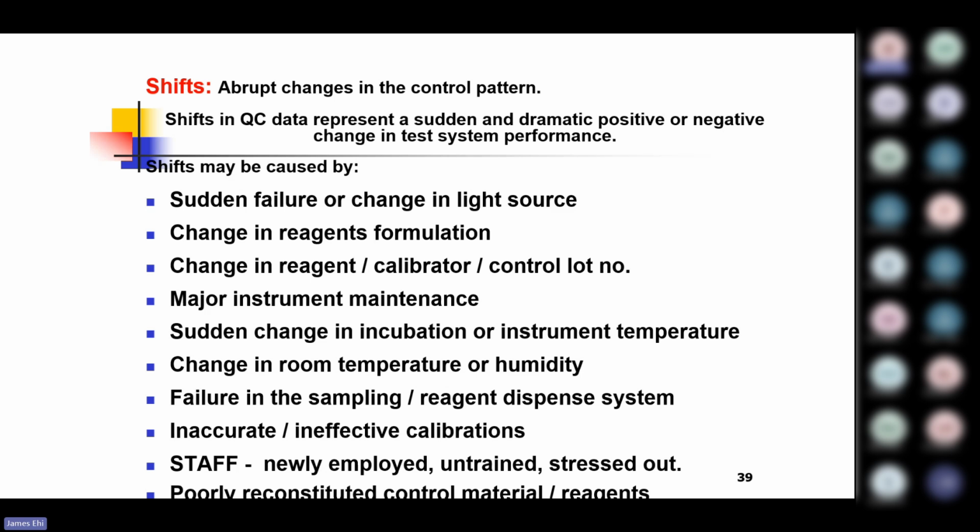So you see the damaging effect the temperature has. And that's why we have air conditioned systems where we keep our laboratory equipment. If you are feeling too cold, please don't switch off the AC. Go and get a laboratory coat, get an extra suit to keep yourself warm, because you might be affecting the performance of the instrument so that we produce shifts, especially hematology analyzers.